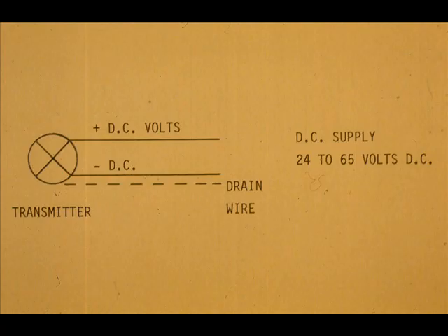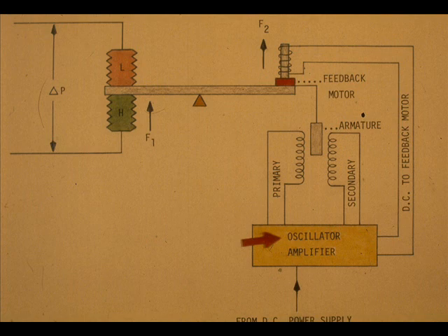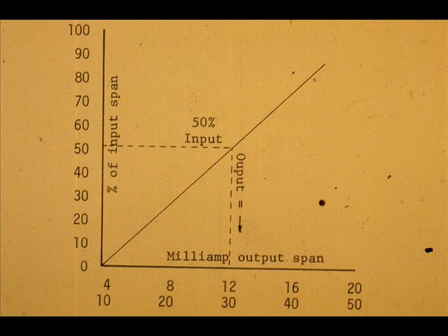The electronic pressure and differential pressure transmitters use two wires for power and signal purposes. They require DC voltage for operation. Currently, 24 volts DC is a popular choice. But some types depend on AC transformers for detecting a measurement change. The AC is generated in the oscillator section. The output span is usually 4 to 20 or 10 to 50 milliamps DC, with the 4 to 20 span being the most predominant.